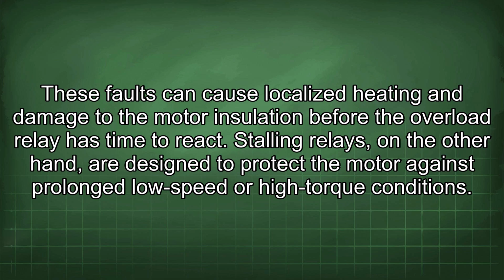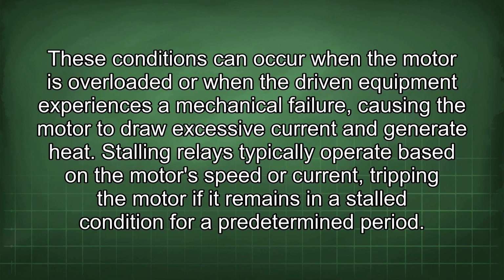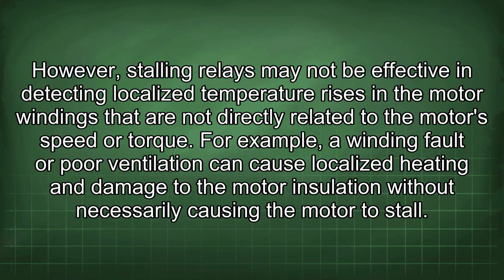Stalling relays, on the other hand, are designed to protect the motor against prolonged low speed or high torque conditions. These conditions can occur when the motor is overloaded or when the driven equipment experiences a mechanical failure, causing the motor to draw excessive current and generate heat. Stalling relays typically operate based on the motor's speed or current, tripping the motor if it remains in a stalled condition for a predetermined period. However, stalling relays may not be effective in detecting localized temperature rises in the motor windings that are not directly related to the motor's speed or torque. For example, a winding fault or poor ventilation can cause localized heating and damage to the motor insulation without necessarily causing the motor to stall.